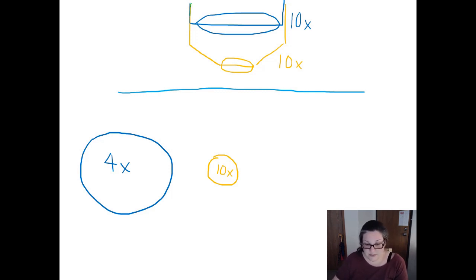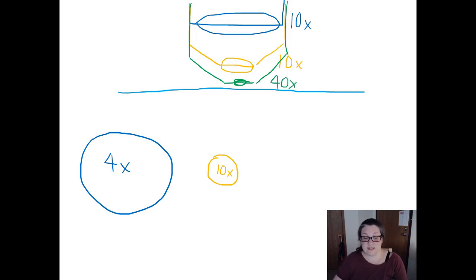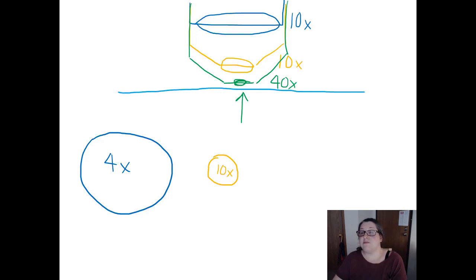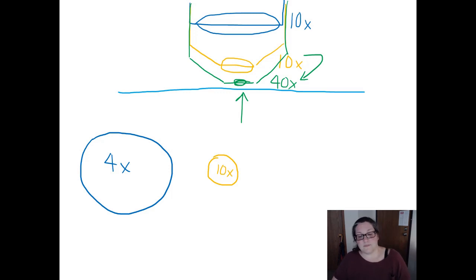When you move up to the 40x objective, you will be very, very close to your slide — about half a millimeter — which is why it is extremely important to never use the coarse focus on the 40x objective, ever, because if you move that stage up you will smash your slide right into the objective. You must also be in focus before changing from the 10x to the 40x. The field of view will also decrease quite a lot with the smaller lens.